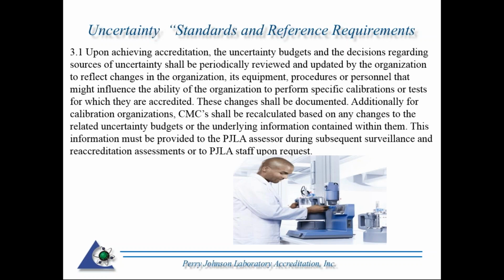So what we're saying here is, every time you have your standards recalibrated, for example, that needs to be reviewed to see if there are any specific changes. Even if you move your facility, you're in a different location, maybe for the better, maybe for the worse, the repeatability studies would need to be done to determine if there was a change in that. And of course, if you change your standards or equipment, perhaps make upgrades, those too would correlate to the uncertainty budgets being reviewed and the CMCs being updated to correlate to the changes in equipment.